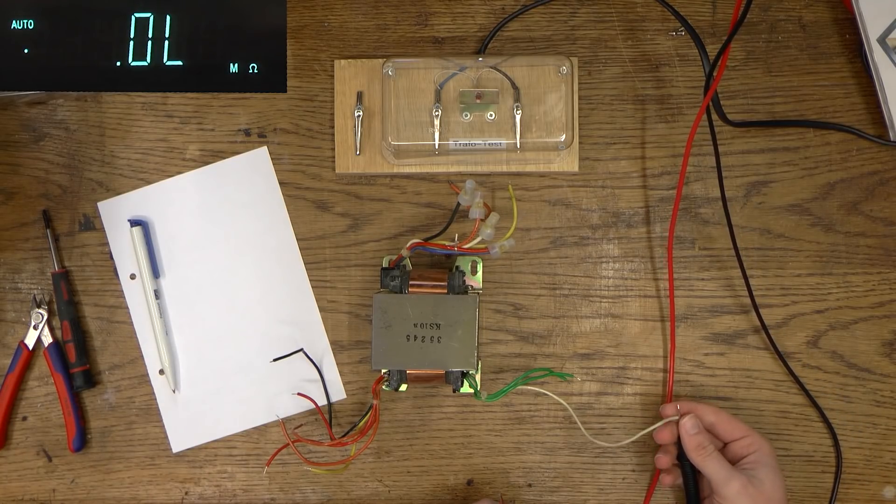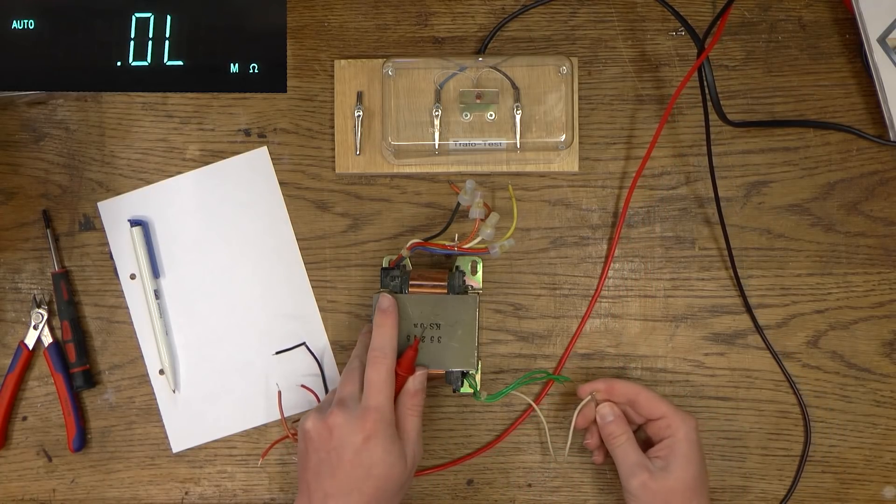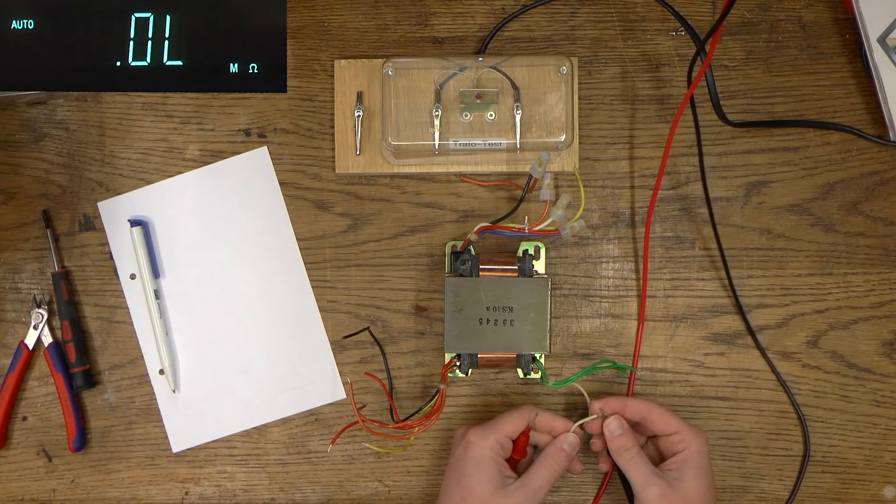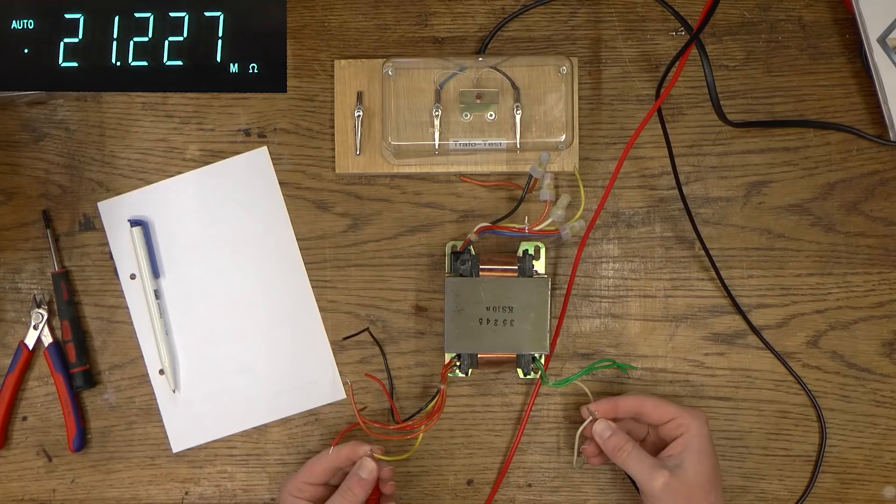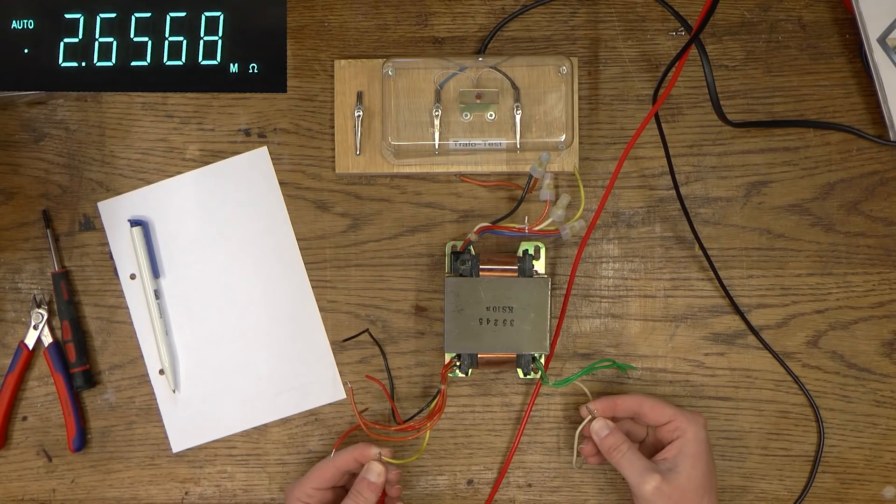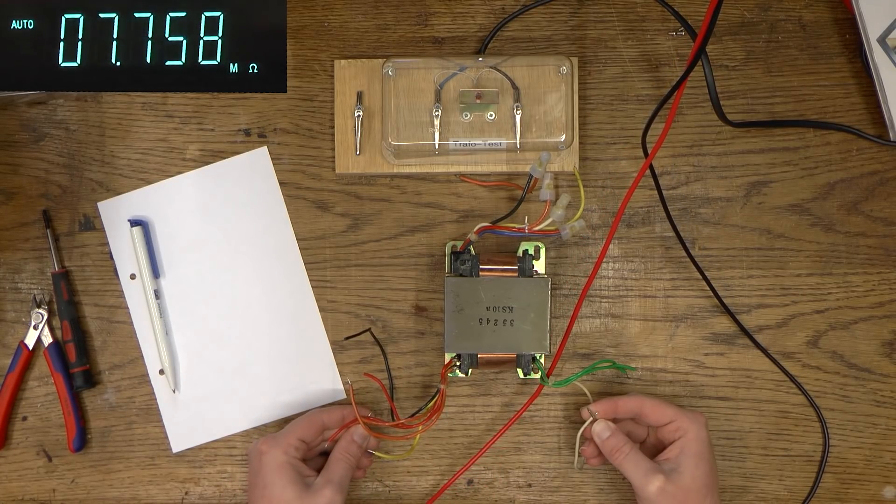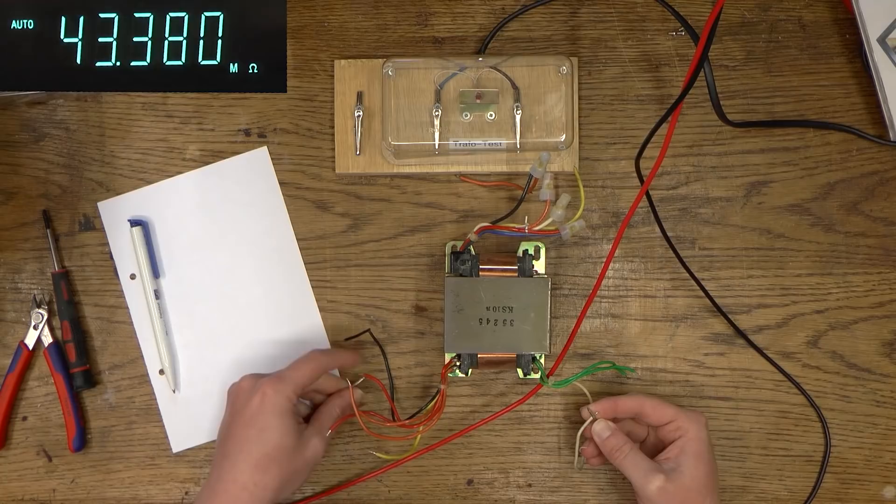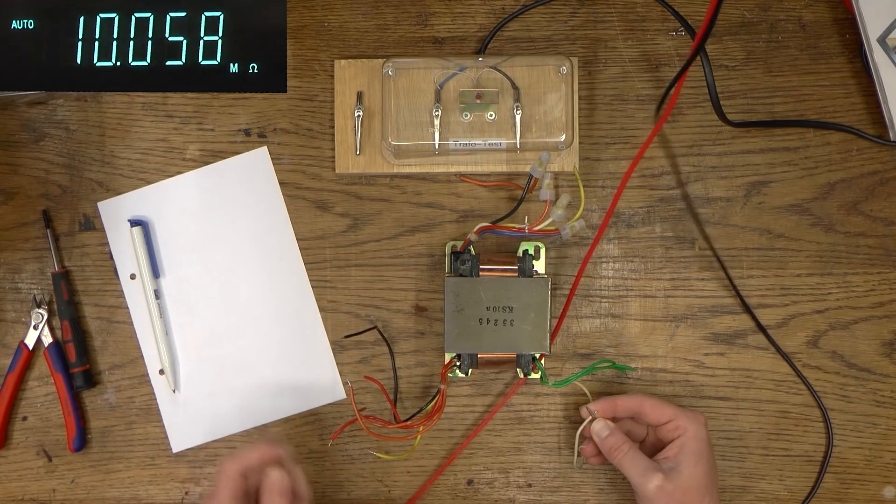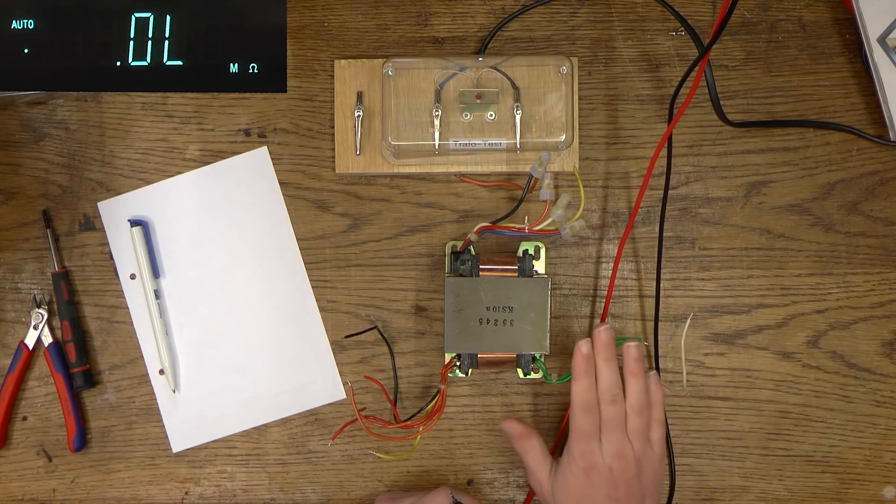So what I'm now going to do is I'm going to make sure that this has no relation to any of the other windings on the other side. So I'm going to keep my probe on the center tap of that winding and I'm going to test all the other windings and we got mega ohms. So that's our first winding. Center tapped winding right there. So that's good.